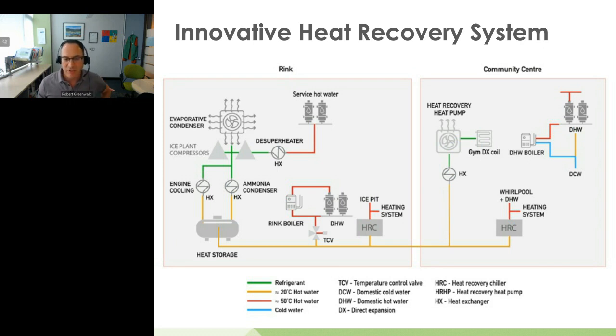When the rink is shut down, as happens in summer and happened during COVID, the heat recovery heat pump on the community center side can still generate heat. Instead of arrows going up to the environment, they go down into the heat exchanger and loop, providing heat for the whirlpool, domestic hot water, and the community center's heating system.